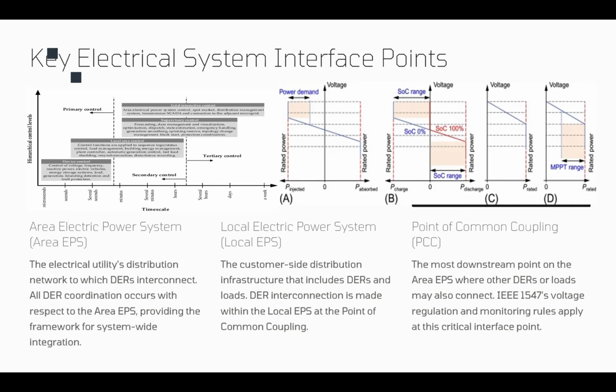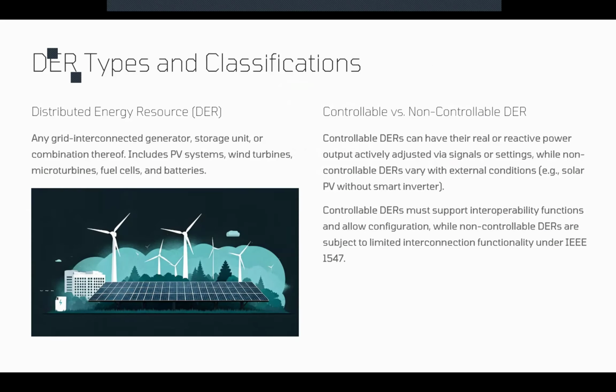So basically, the PCC, the point of common coupling, is the most downstream point on the area EPS, which is where the customer system meets the utility system. Now, every measurement that we conduct, any test that we conduct, or any command that we apply to our system would happen at a PCC. This is the reference point for our work.